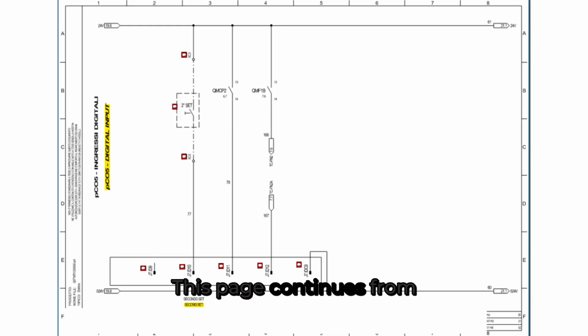This page continues from the previous digital input diagram. At the top, we again see the 24-volt supply, labeled 19.8, running across the top of the page. This low-voltage feed powers all digital input channels, allowing the controller to detect open or closed states from safety devices and interlocks. The first input column on the left includes a set point selection switch, shown as 2-degree set.